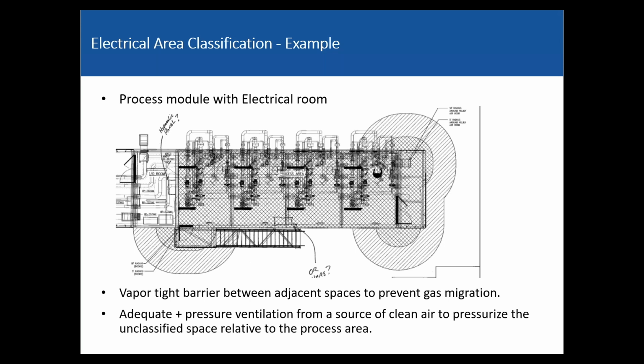So we can't pull our intake from this side, we have to pull our intake from the top. Your air obviously has to come from a non-hazardous area. A couple of interesting things: vapor tight barrier. The codes, NFPA 496 and API 500, don't say what that is. They just say vapor tight barrier. So it's a little bit debatable.